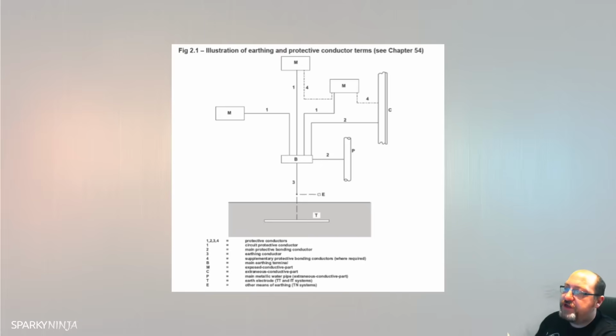You'll have an illustration here, and you can see you've got your earth electrode, main earthing terminal, and here we have the main earthing terminal B. P is a main metallic water pipe, so that's an extraneous conductive part. C is extraneous conductive parts such as steelwork, and you'll notice you have this number 2 going to P and to C - those are main protective bonding conductors going to the two extraneous conductive parts.